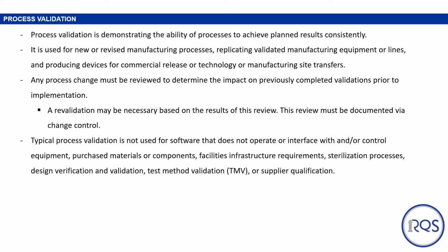Typical process validation is not used for software that does not operate or interface with or control equipment. It's also not typically used for purchased materials or components, facilities infrastructure requirements, sterilization processes, design verification and validation, as we discussed in Module 2, test method validation or TMV, and also supplier qualification. Each of these has its own unique validation type processes that we will touch on at a high level shortly.